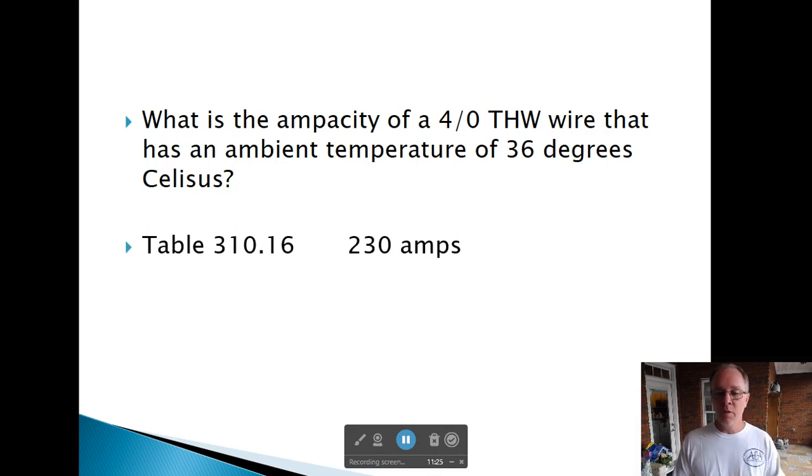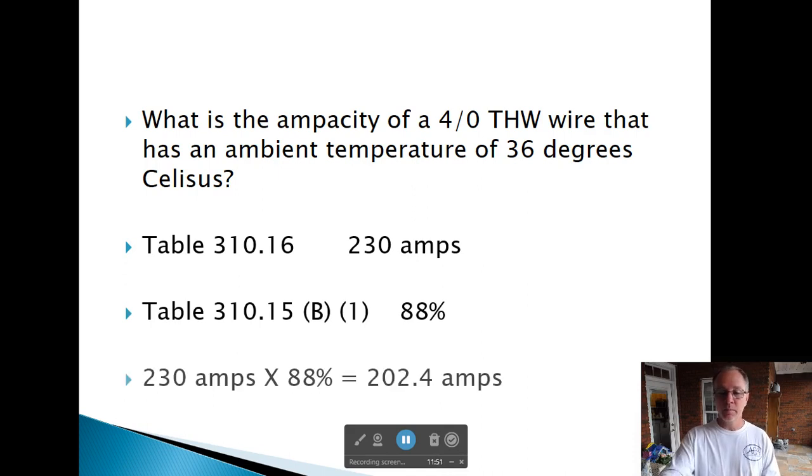Hopefully you're back and hopefully you got your answer. Table 310-16 says 4-Aught THW copper has an ampacity of 230 amps. Table 310-15-B1 says we're going to multiply times 88%. So I got 202.4 amps, so 203 amps. It's going to be a 200 amp wire. Hopefully you got that one right.